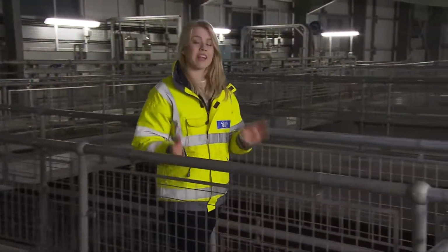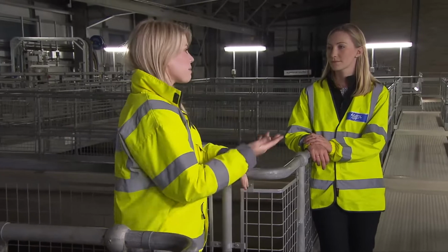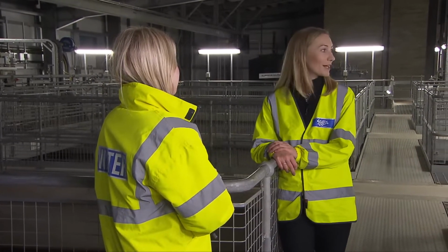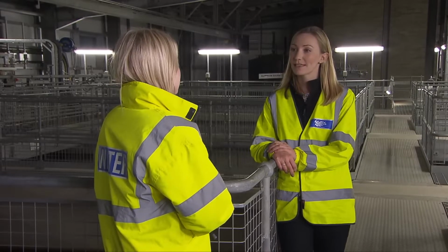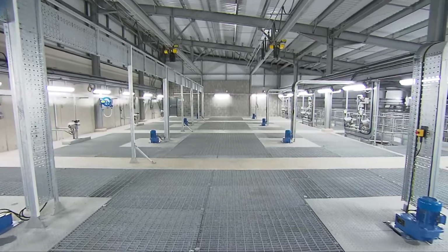Here to talk us through the next stage is Hannah, who is our process scientist. So Hannah, could you tell me more about after the treatment of the chemicals? Yeah, so after the coagulant is dosed, the water enters the flocculation chambers, which are over here, where it's slowly stirred, causing the particles that have come out of solution to collide together and form flocks.